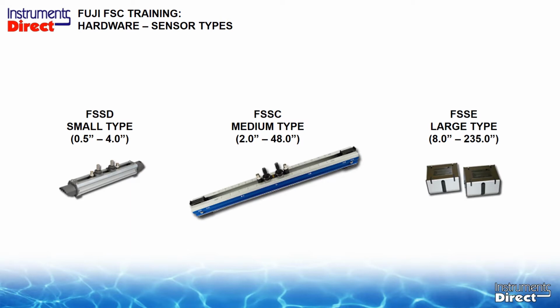Here we go. This is the small pipe transducer. The small pipe transducer on the left, FSSD, is 2 megahertz for pipe sizes 1/2 to 4 inches. The transducer in the middle is the FSSC, the one we were just talking about. This is 1 megahertz and it works on pipe sizes 2 to 48. Wow, that's kind of interesting. So it's pretty much the workhorse. The transducer on the right is the FSSE, which is a 0.5 or 1/2 megahertz. It is not on a rail. This is reserved for very large applications, and you can use it for 8 inches up to 200 inches. So very, very large pipe applications is what you would use that transducer on.